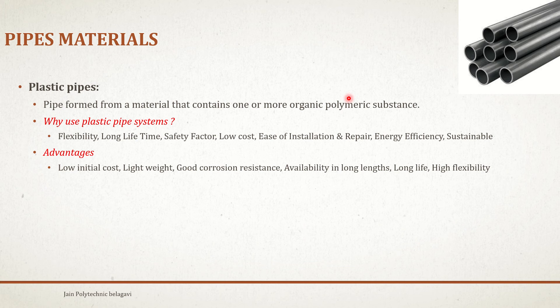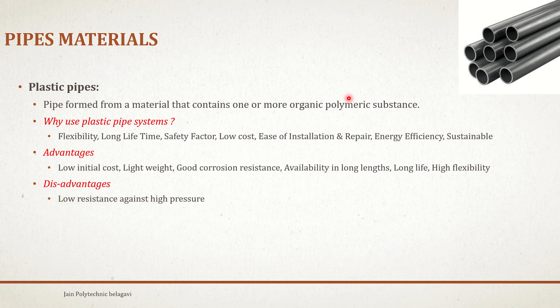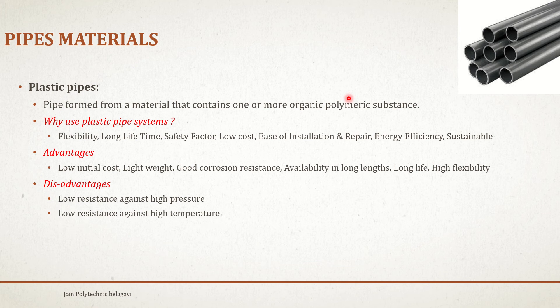Advantages of plastic pipes: low initial cost, lightweight, good corrosion resistance, available in long lengths, long life with high flexibility. Disadvantages: low resistance against high pressure because the pipe thickness is less, and low resistance against high temperature because it is a flexible material that melts at high temperatures, and poor fire resistance.